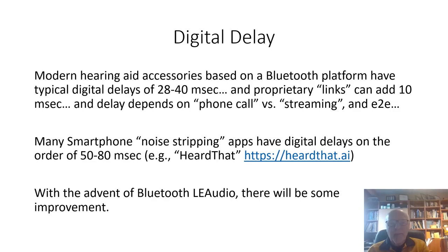And accessories may be something as simple as a TV listening device, where the device sits on your TV, converts the sound into Bluetooth, which is then picked up by the hearing aid. Well, that device, although it's a wonderful device, actually has a little bit of a delay. And from the manufacturer specs, it's not unusual to have them on the order of about 30 milliseconds. So you have to add that to any other digital delay that a person may get.